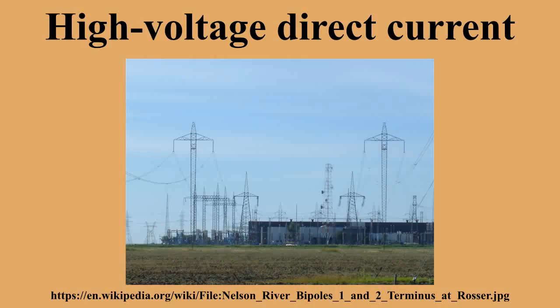The modern form of HVDC transmission uses technology developed extensively in the 1930s in Sweden and in Germany. Early commercial installations included one in the Soviet Union in 1951 between Moscow and Kashira, and a 100 kV, 20 MW system between Gotland and mainland Sweden in 1954. The longest HVDC link in the world is the Rio Madeira link in Brazil, which consists of two bipoles of plus or minus 600 kV, 3,150 MW each, connecting Porto Velho in the state of Rondônia to the São Paulo area. The length of the DC line is 2,375 kilometers.